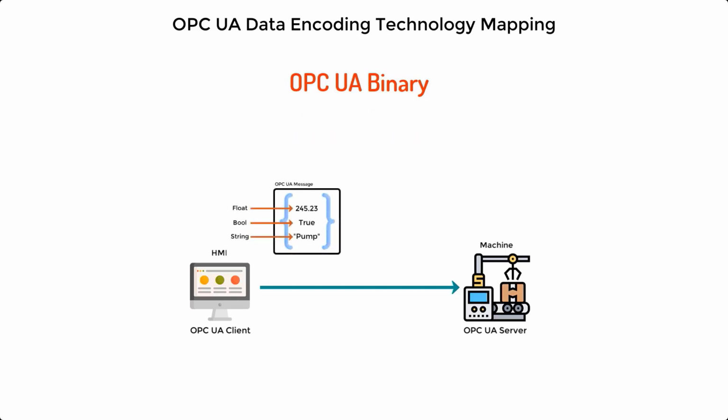So, to encode in OPC UA Binary format, all the primitive data elements that make up a structure are sequentially written to a binary stream using clearly defined rules. For example, in OPC UA Binary Encoding, the rule states that a Boolean value shall be encoded as a single byte where a value of 0 is false and any non-zero value is true.